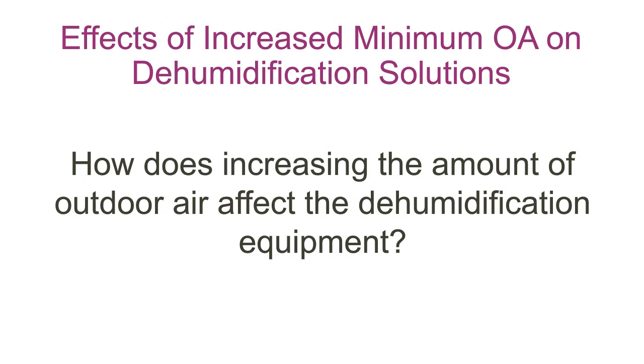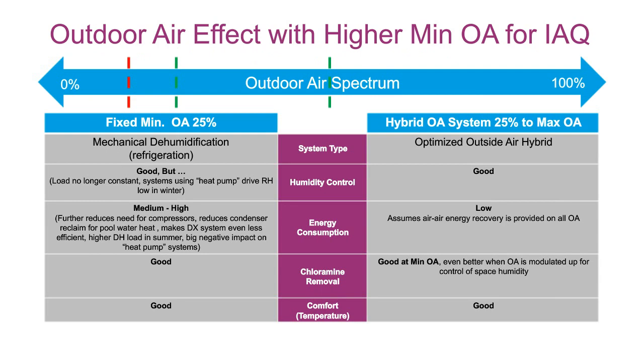So then looking at if you increase that minimum outside air in order to handle your indoor air quality, what does that do to the dehumidification equipment that we've been talking about? Well, in the case of the mechanical dehumidifier fixed at 25%, the humidity control is still pretty good, although the systems that try to use a heat pump could drive the RH pretty low in the winter. Your energy consumption is now going medium to high because you don't really need the compressors now. You're not going to get nearly as much reclaim possibility, only really a few months in the summertime, and it makes that DX system even less efficient.